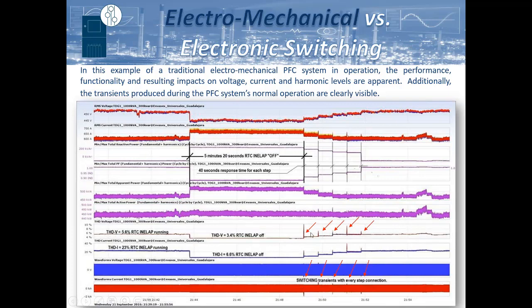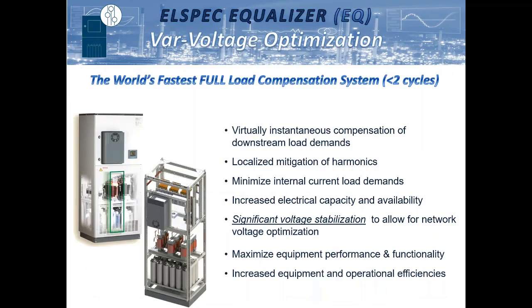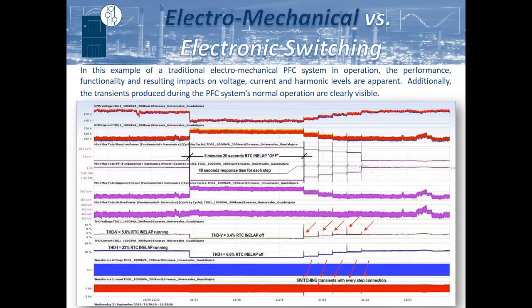You can also see that every single time those electromechanical contactors come in, transients are induced. Those transients are not just local to that system, but propagate throughout the network and can have an adverse effect on other equipment or the process itself. Also, the capacitors internal to these power correction systems are most susceptible to things like voltage levels as well as transients and harmonics. This is why quite frequently, when you go into a facility that has a traditional power factor correction system, they may not be fully functional or functional at all, because every single time these transients hit, they put little pinpricks in the capacitor insulation.